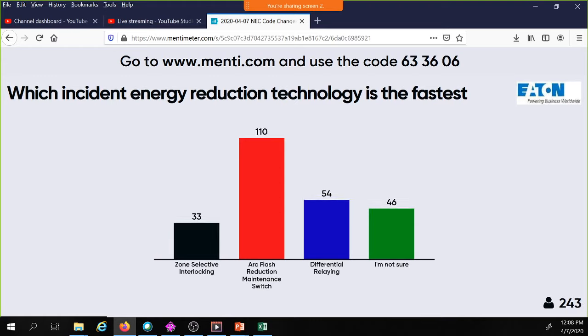There's no microprocessor. When you get into zone selective interlocking or differential relaying, most of those other technologies outside of the arc quencher, which we will talk about, have a brain, and that brain has to, A, detect that current is flowing, B, compare that with a set point and make sure it's above the set point, C, possibly in zone selective interlocking, check for a downstream signal, and then if it's there, make a decision, and then trip. And that process on ZSI, zone selective interlocking, could take up to 0.07 seconds.